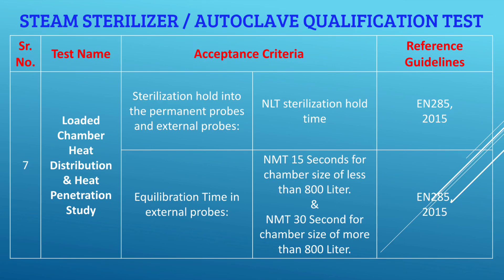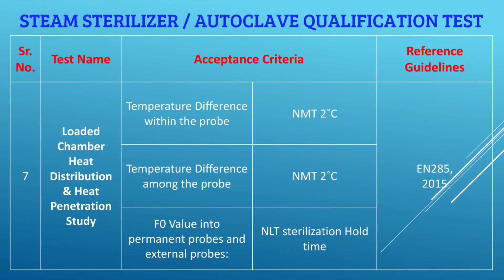The equilibrium time in external probes should be not more than 15 seconds for a chamber size of less than 800 liters, and not more than 30 seconds for a chamber size of more than 800 liters, as given in EN 285:2015. Temperature difference within a probe should be not more than 2°C, and among probes also not more than 2°C. The F0 value in permanent and external probes should be not less than the sterilization hold time.